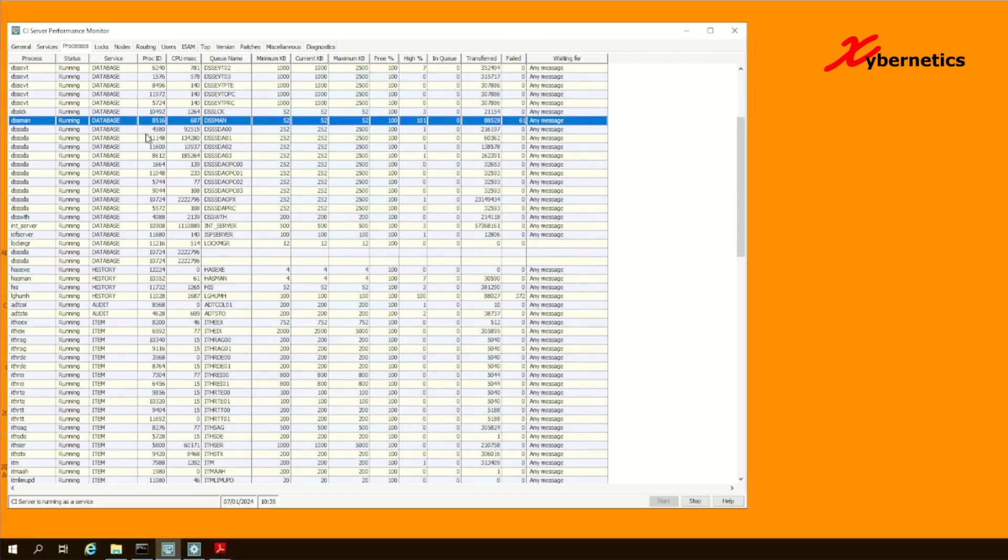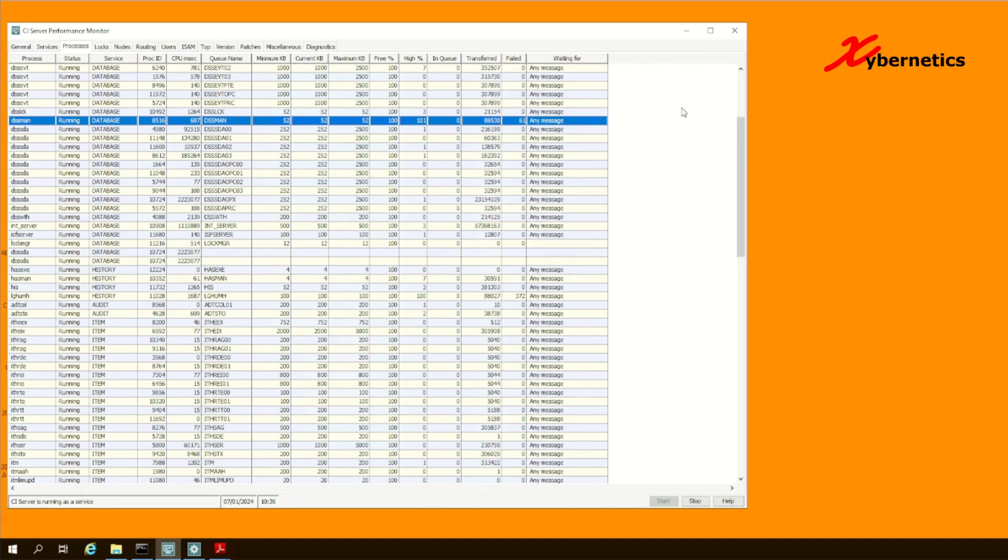The impact of DSS man failing would be things like your OPC UA client will fail to start or fail to connect. If you're curious, what DSS man does is it actually acts like a scheduler between DSS DA and DSS EVT for event processes to coordinate packet exchange between those two processes.